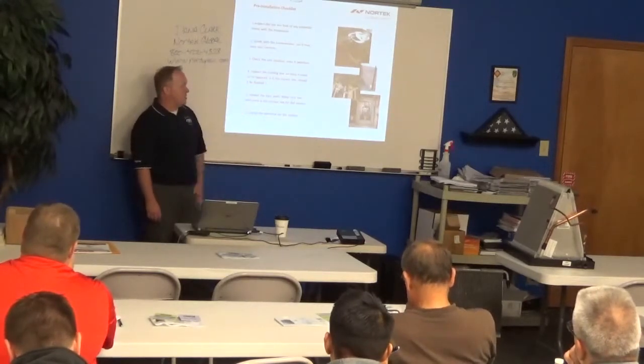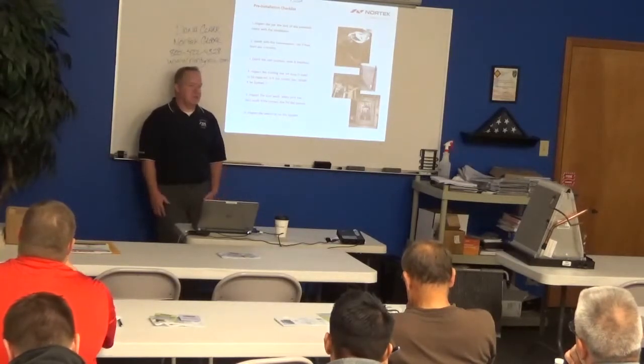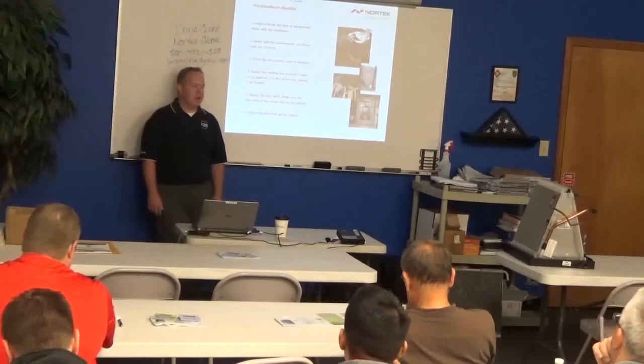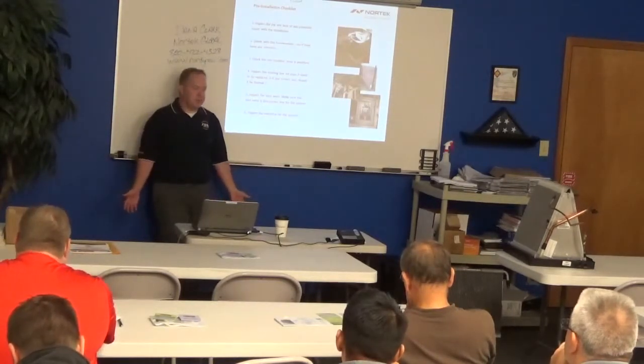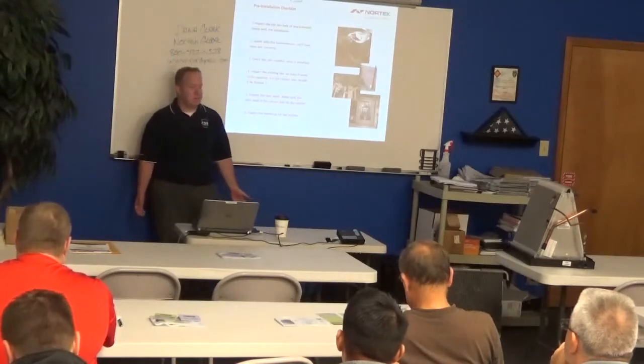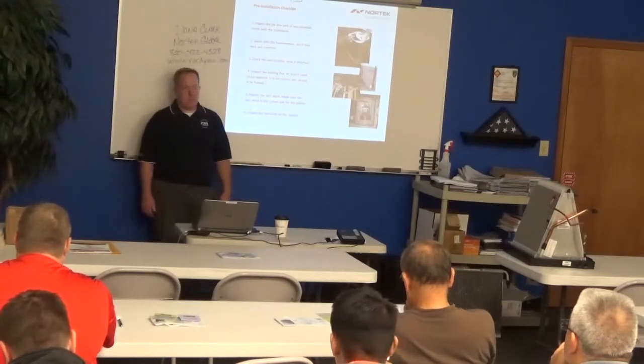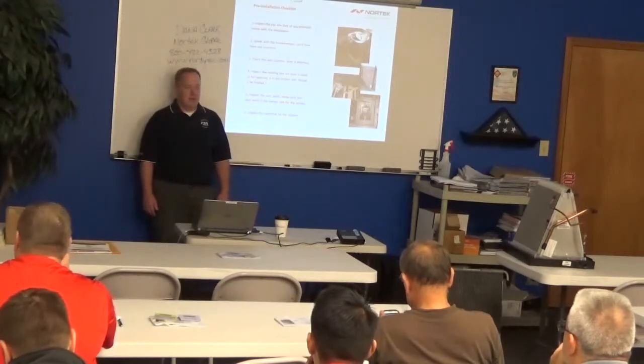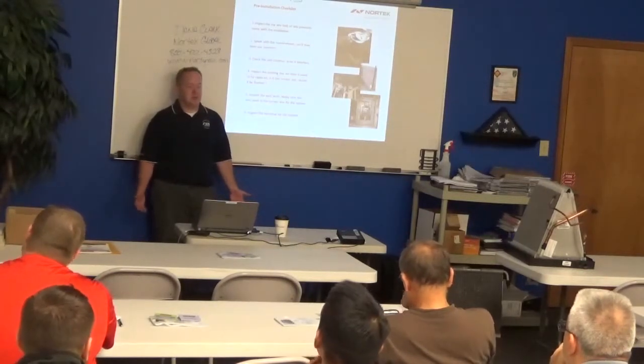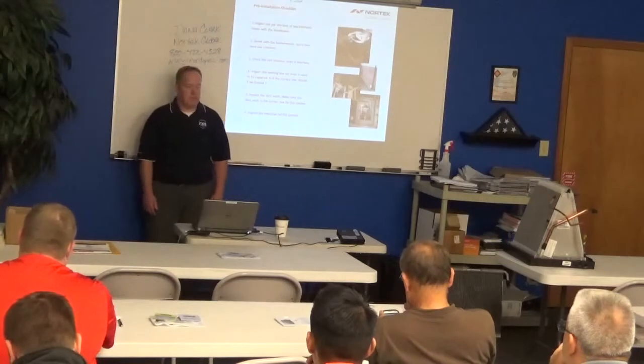We get asked a lot about things like line set sizing. Okay, line set sizing is fairly straightforward. There really isn't an awful lot of mystery there. You can certainly use this on an existing line set, so long as you know that it's properly sized for the application that you want to do, and that it's serviceable, it's not damaged, and that it's clean. If you flush it, and you know that size-wise you're going to be okay, that the actual physical construction of that existing line set is going to be useful to you, I'll give you a great example.